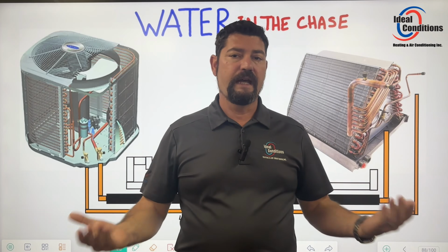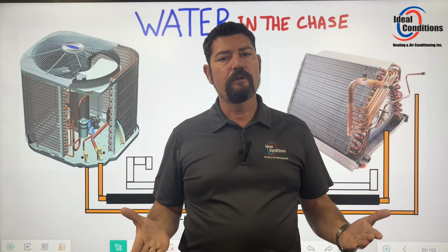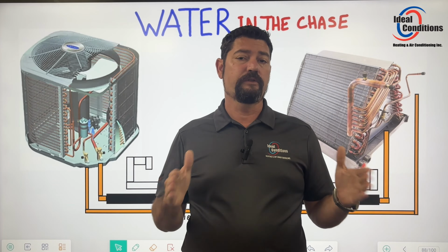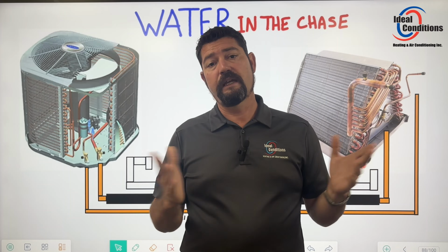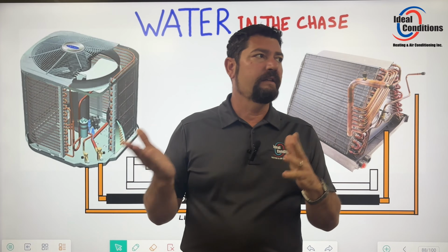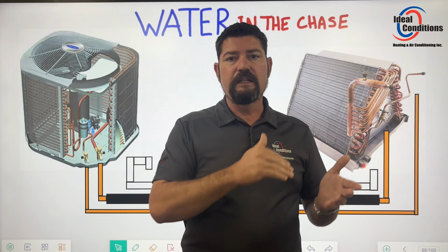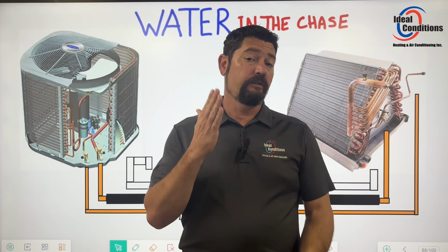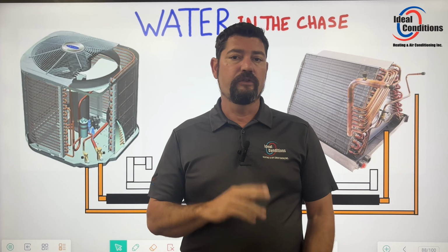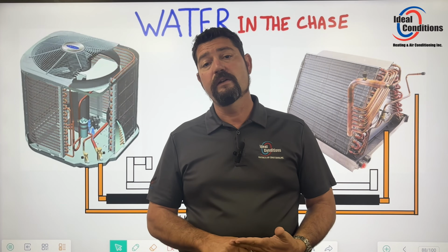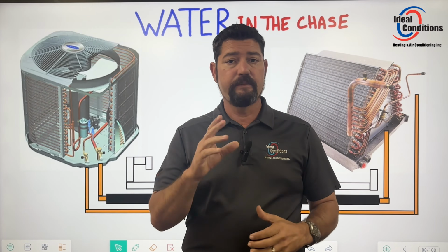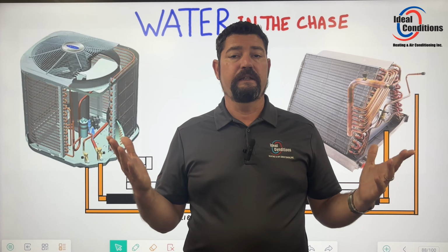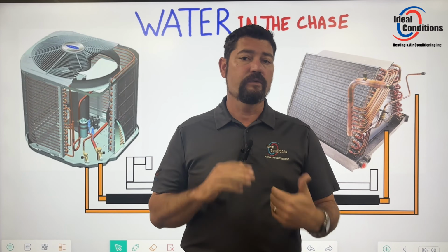The insulation that you have on that copper is probably not half-inch wall, probably 3/8 wall, probably thin. It may even be bare in a few areas where it's sweating. And in some cases, maybe there's no insulation at all. By the time it goes out the eave and down the side of the structure, the insulation, if it was there, is dry rotted, no longer there, or it never had it. Critters like to climb up that, clawing at it, eating it. At the end of the day, it's missing a lot of insulation, or there is none.